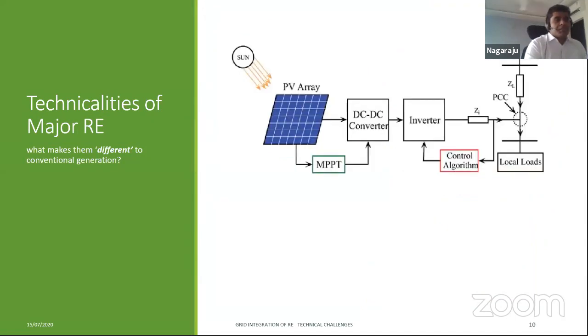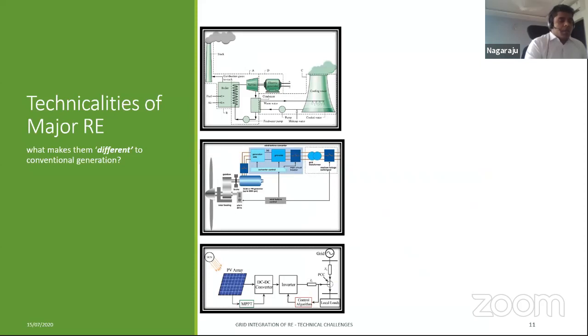Solar, again, same story. The power electronic converters are acting as a medium between the source and the grid to transmit the energy produced in the PV arrays from DC to the AC side grid. Then again, a similar story here. The wind farms and solar farms have large geographical areas with cables and transformers, PV transformers. So they all add up to the reactive power requirements. Okay. Those are basically the fundamental differences.